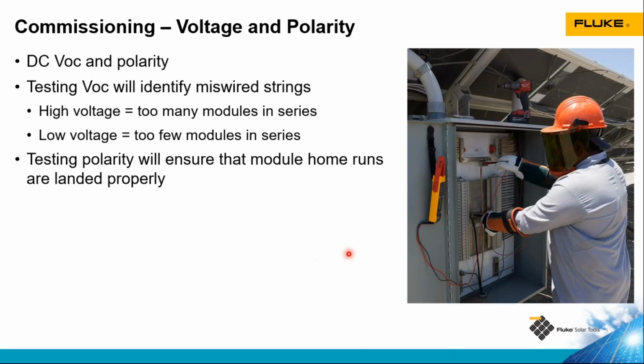So in this picture here, we've got a large commercial combiner box. Our negative conductors are at the top of the box. Those are all being bussed together. Our positive conductors are coming in the middle of the box to these fuse holders with the bus bar in the middle. At commissioning, the fuses are not installed yet, so you can very easily find reverse polarity and oftentimes fix it before it becomes a larger problem when the fuses are closed.